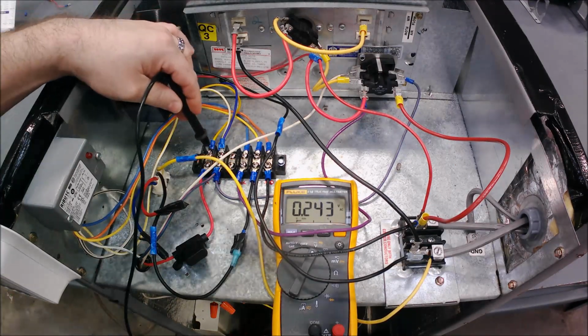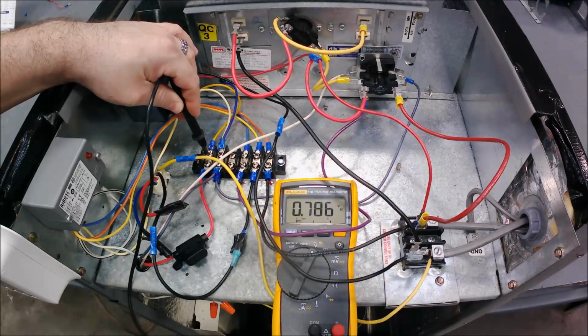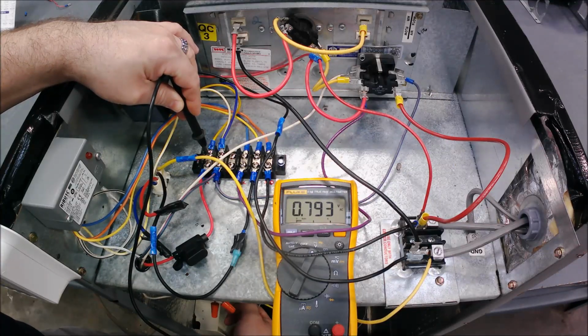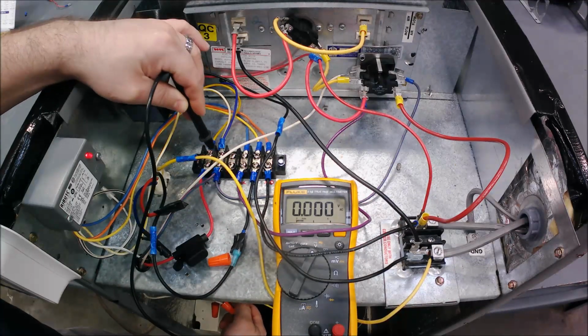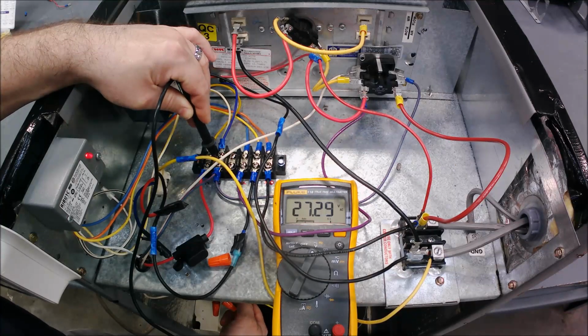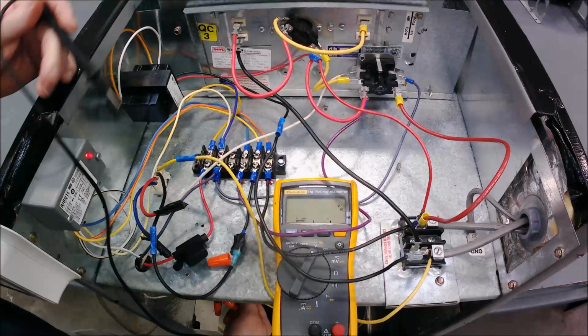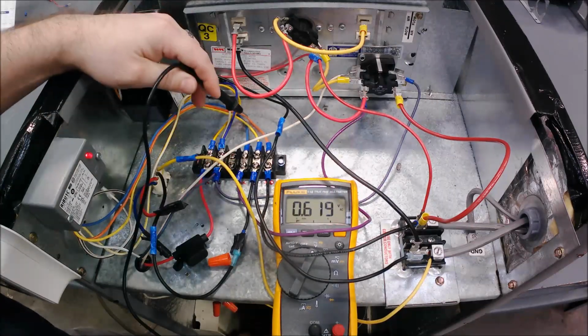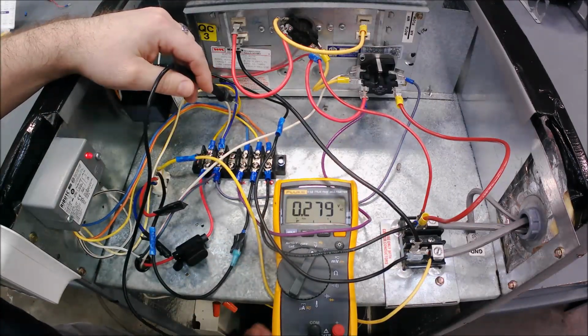If we wanted to check the voltage to the coil, I would need to go down to the low voltage that we wired, take that thermostat or that cap off, and I've got 27 volts on my rib relay coil, and you can see over here that that little red LED light is on.